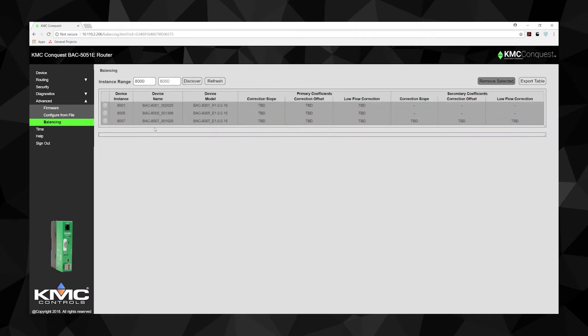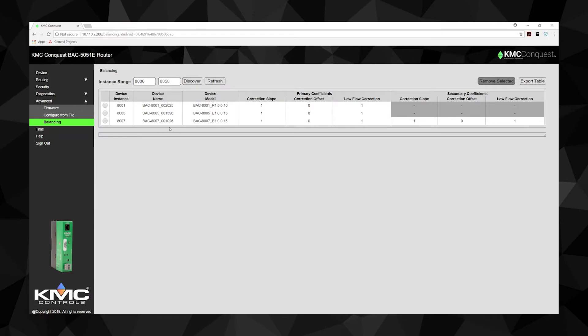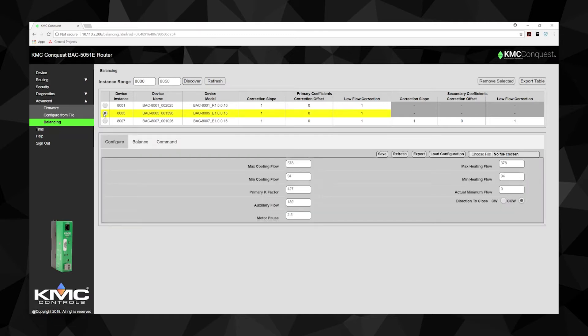This will discover all the devices, not only VAVs, so look for the devices with flow coefficients indicated. These will be VAV controllers. Select a VAV unit from the list to balance. The background for this unit will change to yellow.